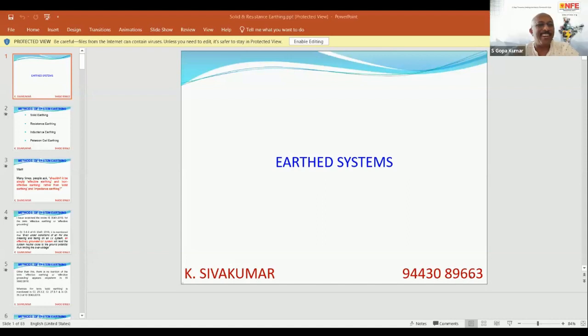Rahul, yes, of course, current has to return. Kirchhoff's law always says that the current will return to the source neutral. Irrespective of the length, if the transformer is feeding, the fault current will go back to the transformer neutral. If the generator is feeding, the fault current will go back to the generator neutral. Yes, if both the neutrals are linked together and not isolated, unfortunately, but rules mandate isolation of the neutral. Suppose I'm assuming that both are interconnected, there will be a potential rise on the other source neutral.